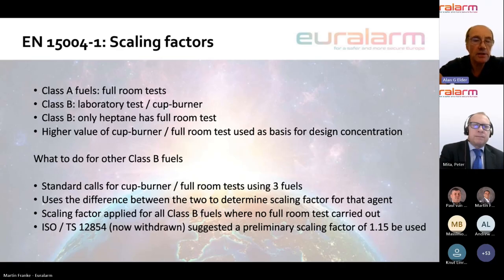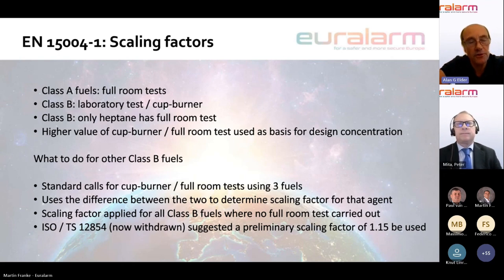What the standard now recommends, and I'm saying recommends because this is actually an informative annex, so it's not a normative annex in the standard. It does say that what you should do is carry out a cup burner and a full room test for 3 fuels. And those 3 fuels would be heptane, acetone, and methyl alcohol. And what you do is that you take the highest of the values of those and you apply a scaling factor. So if the full room test for the worst case of those three fuels required a 40% safety factor or scaling factor, you would apply that then to those materials.